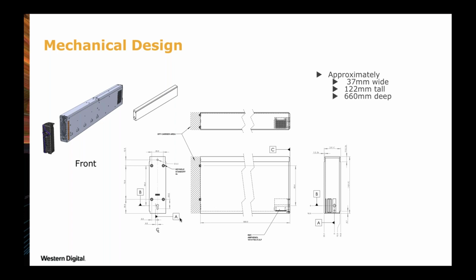It is not. There is a limit in terms of the connector that's in there, how much current can go through it, but the airflow is not really even a part of this device. This device needs to be inserted into an enclosure. Western Digital has one design of that enclosure. There could be many designs of that enclosure, and that enclosure has to handle the thermals. Depending on how much power you're going to consume in the device, it will be a factor of how much air and what temperature air you want to assume, and all those things come into play. So I did not intend to specify that as part of this design submission, because they're actually controlled outside of this design.